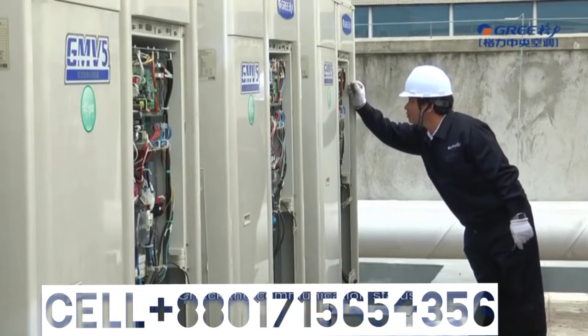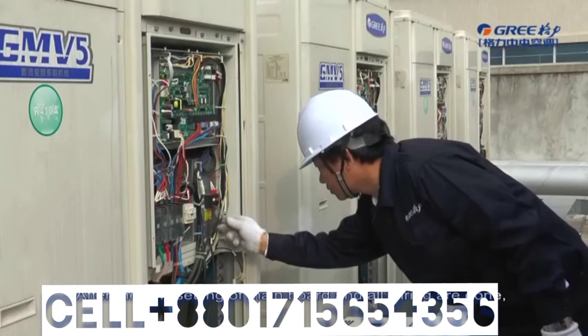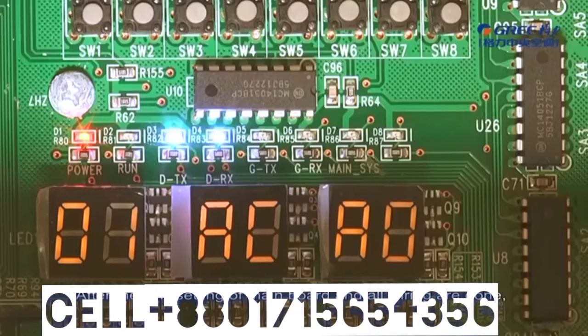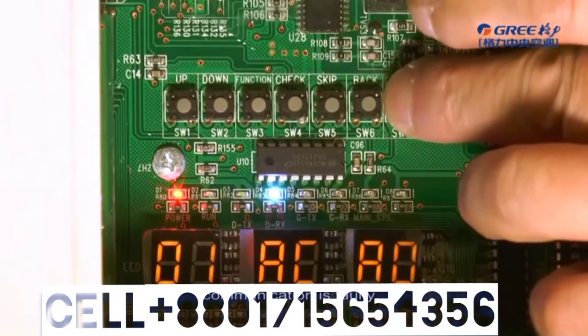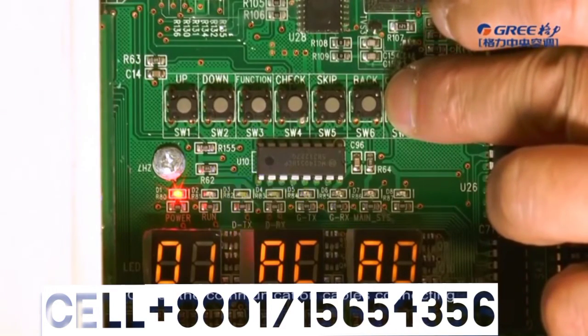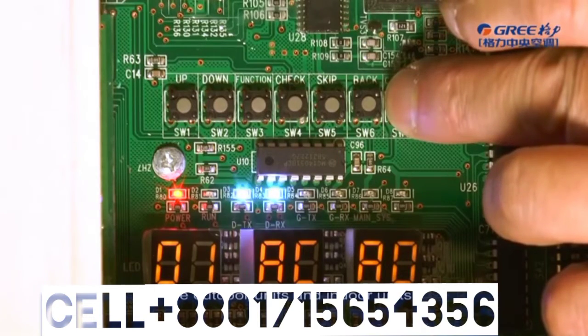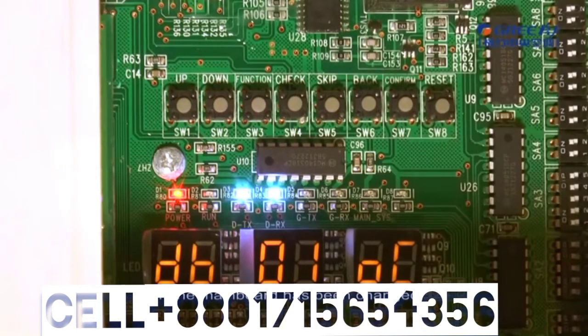3. Check the communication status. After the DIP setting of the mainboard and all wiring are done, power on the outdoor unit and check whether the D3 and D4 LEDs are flashing. If the LEDs flash, the outdoor units and indoor units communicate normally. If the LEDs do not flash, communication is faulty. Check the communication cables connecting the outdoor units and indoor unit. If the mainboard has been changed, the system should be debugged again.